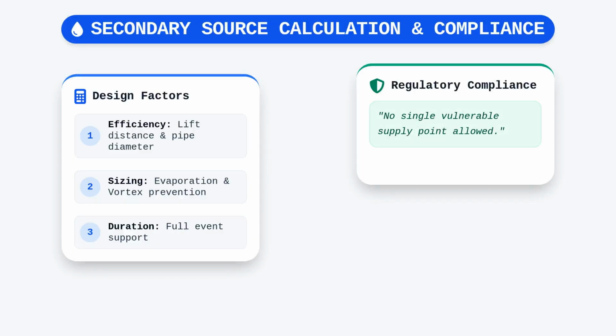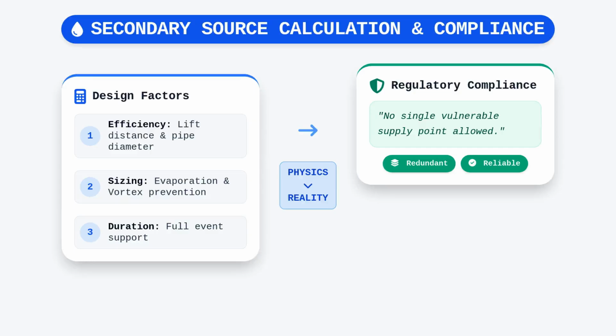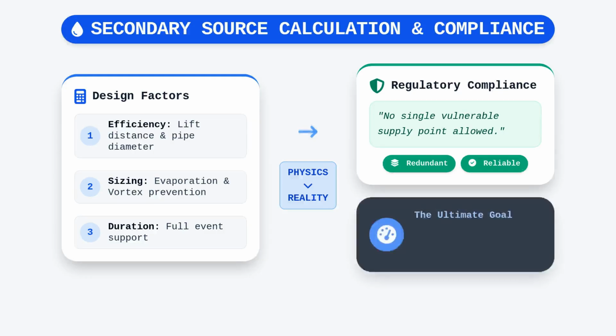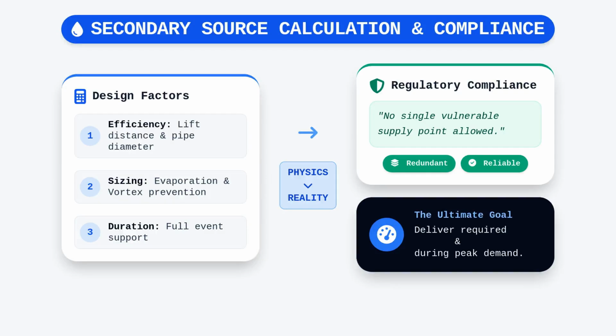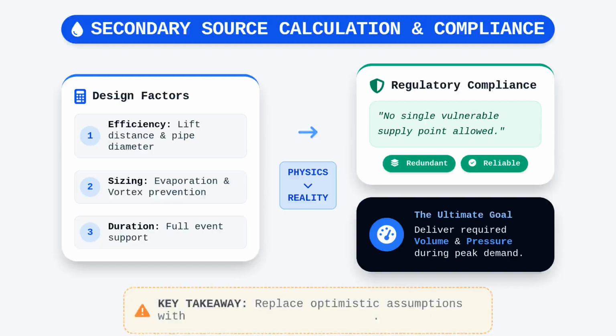Regulatory compliance further dictates that these systems must be reliable and redundant, meaning you cannot rely on a single, vulnerable supply point for a critical facility. Whether you are dealing with a simple loop system or a complex mesh grid, the goal remains the same. The system must deliver the required water volume at the correct pressure during the peak demand phase of the suppression system operation. Taking the time to perform these exhaustive manual checks ensures that your design is not based on optimistic assumptions, but on the raw reality of physics and hydraulic constraints.